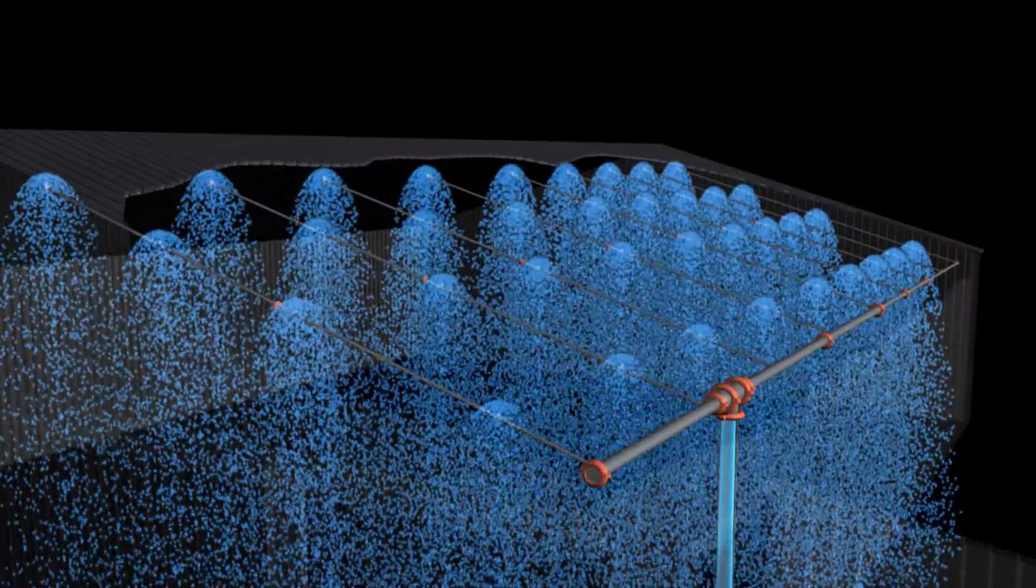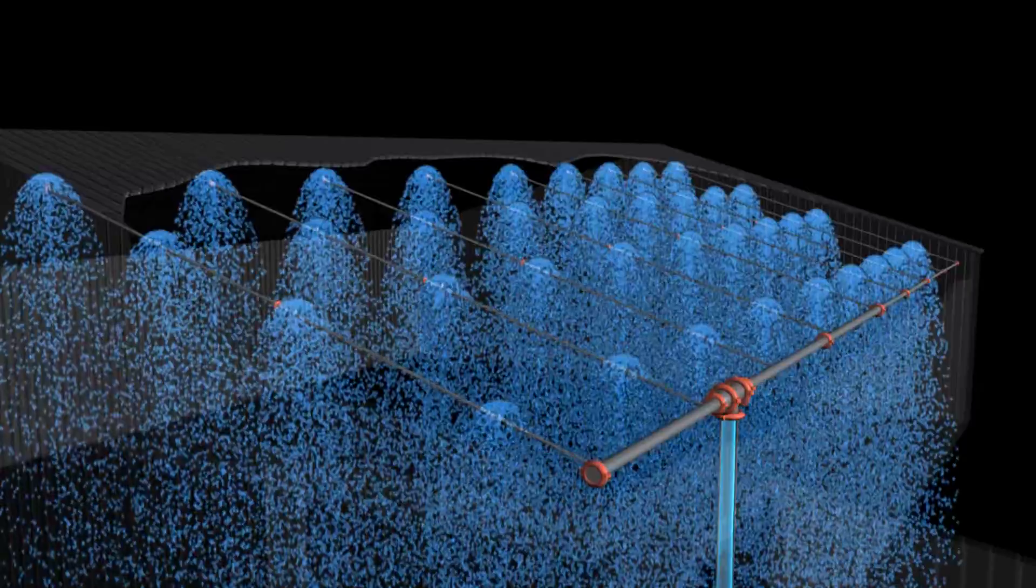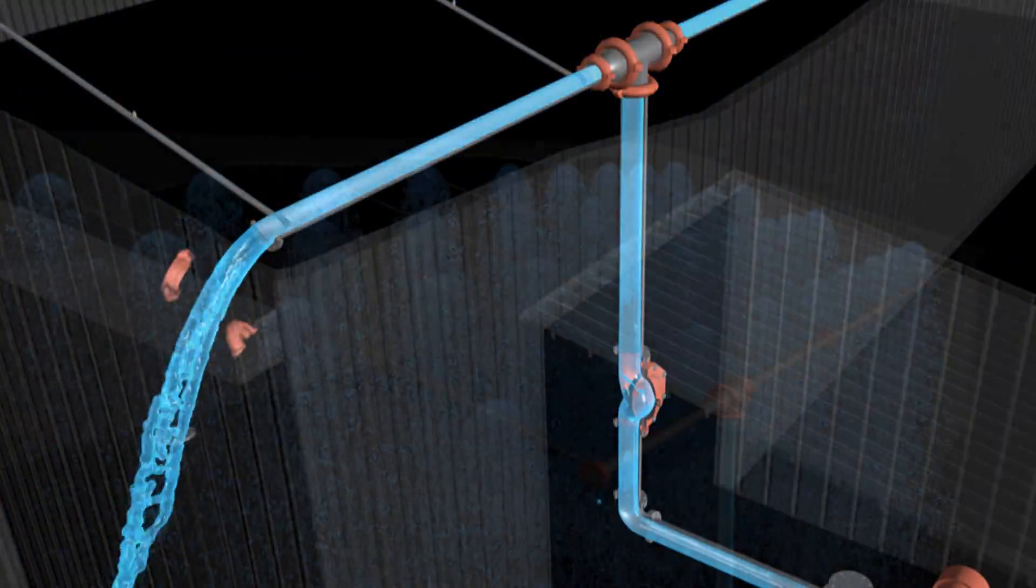The sudden opening of the deluge valve can create a surge condition that can cause a sprinkler head or fitting to fail.